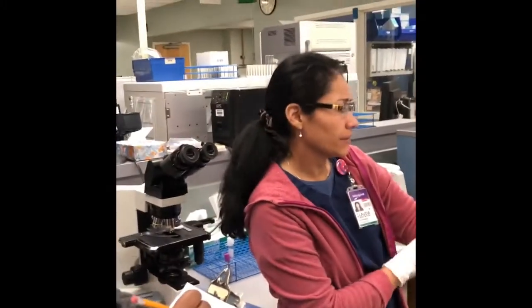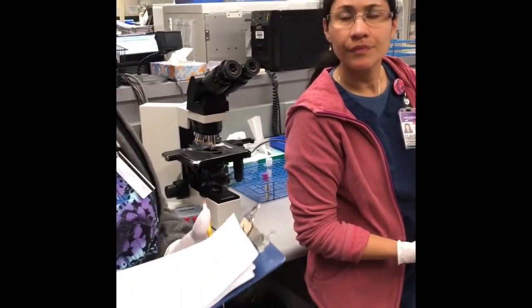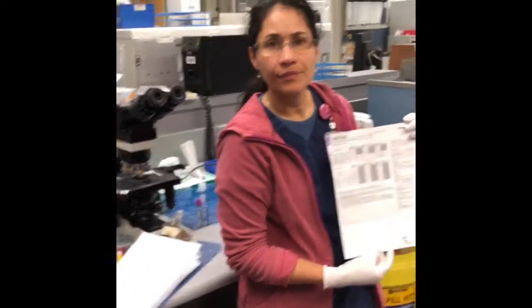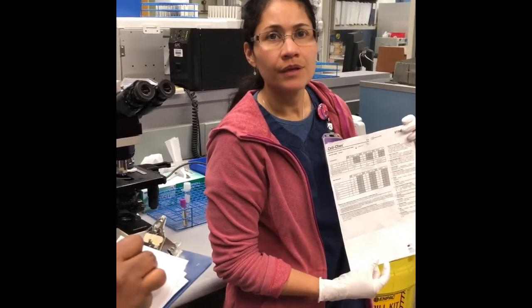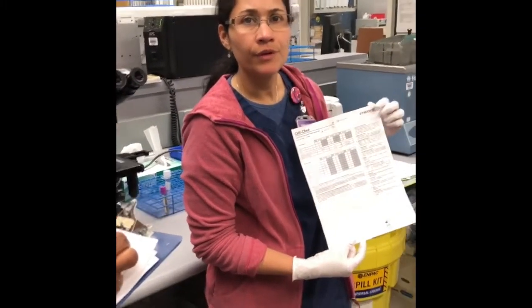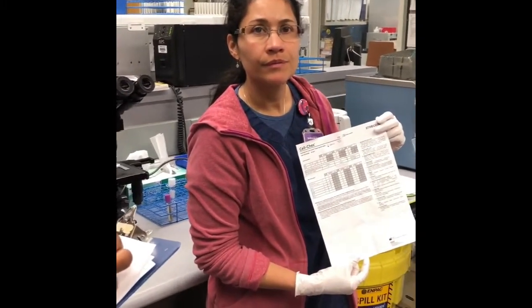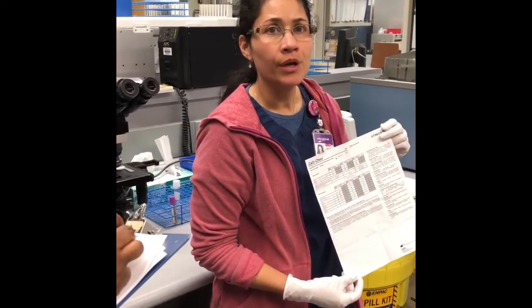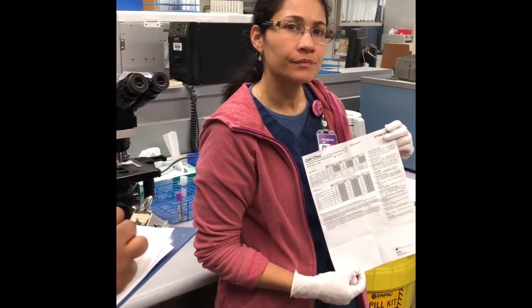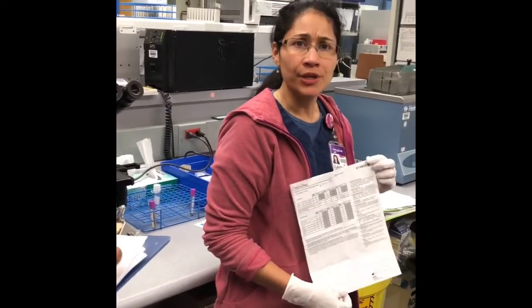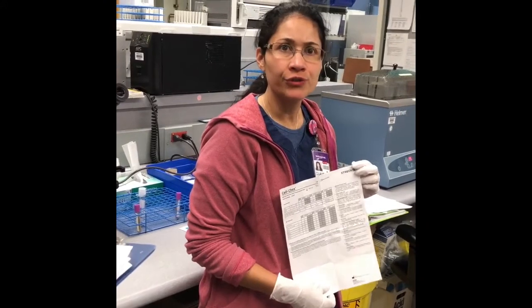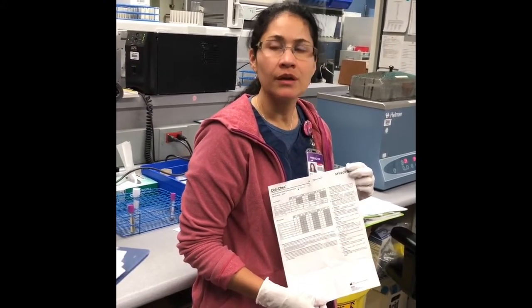Can you go over again? Some people weren't here. Were you here, Sharon, when she started? Regarding the QC and the rotation of the QC, and also the background if you had to do dilutions. That's a part of it too, right? If you have to check the background fluid if you're using it for a dilution. Yes, that's part of QC. You can monitor dilutions using your QC.